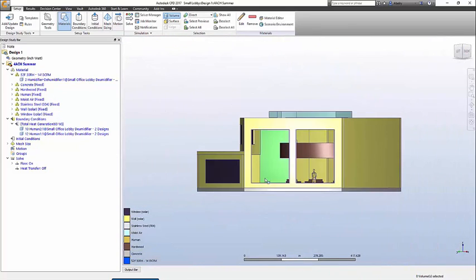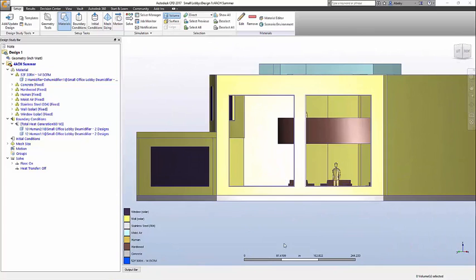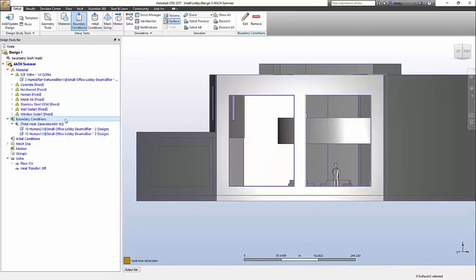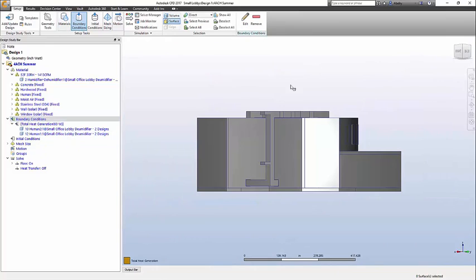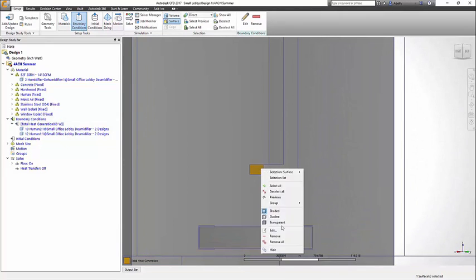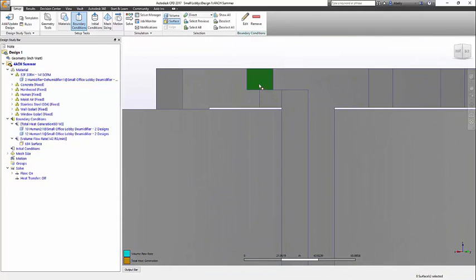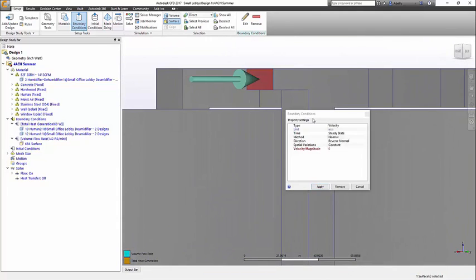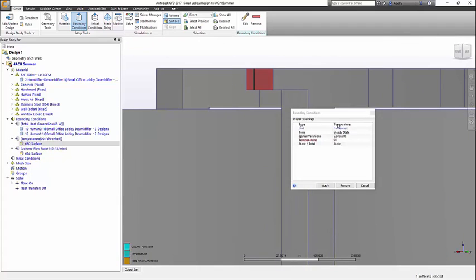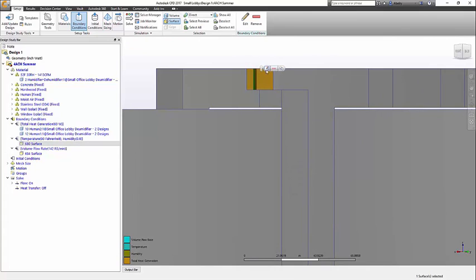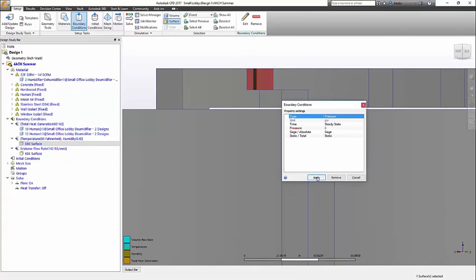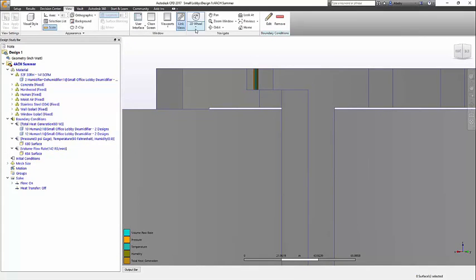That completes the material setup, and we are ready to define the outside makeup air with some boundary condition. After the air is combined from the two low returns, you will need a flow rate of 102 CFM, or 10% of what the HVAC unit on the roof is producing. Now you will need to define an ambient condition for the outside air to be pulled back into the model. For this summer case, in the U.S., we used 90°F and 90% relative humidity.